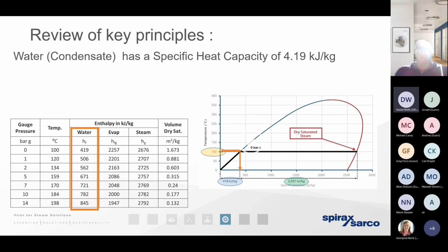So if we're just generating steam in a kettle in our kitchen at home at 0 bar gauge, that water needs to contain 419 kilojoules before it is at boiling point, because after all, water boils at 100 degrees. So the maths is simple: 4.19 multiplied by 100. Now that's how much energy the water needs to contain before it boils. If we're putting water that is already at a significant temperature, with a significant energy content, into that kettle before it hits boiling point, then of course we need to top it up with far less energy in order to achieve that.